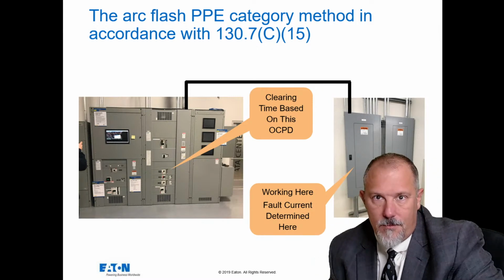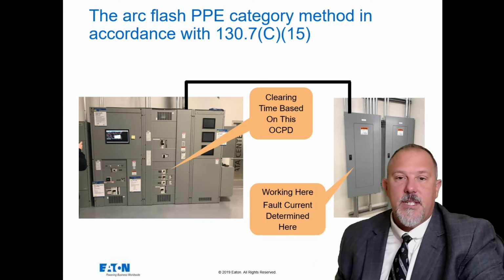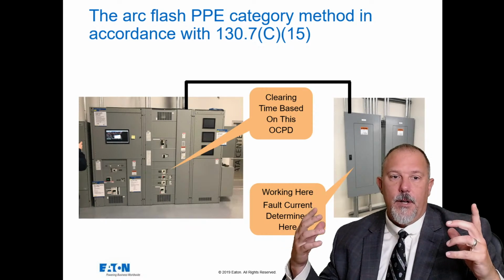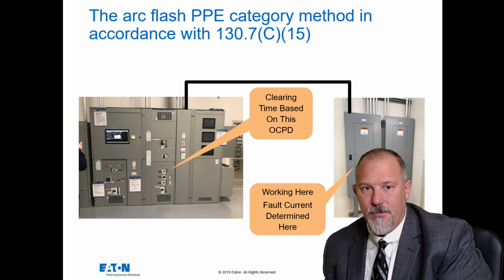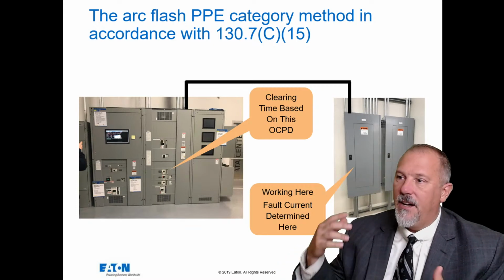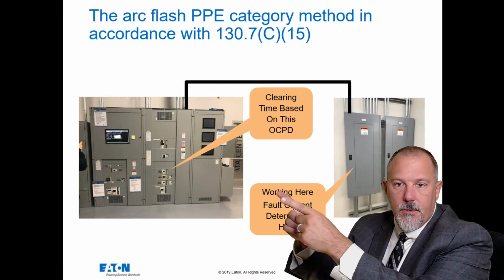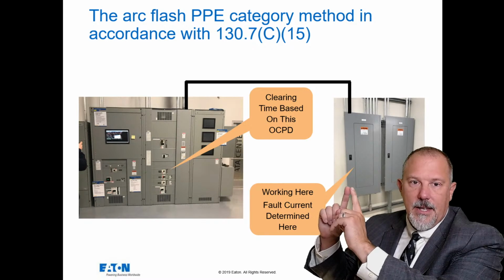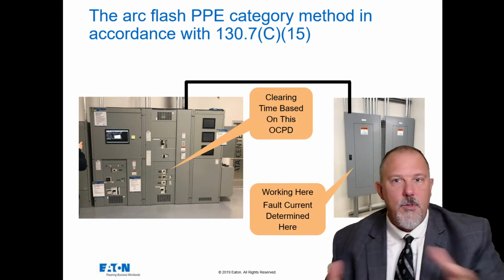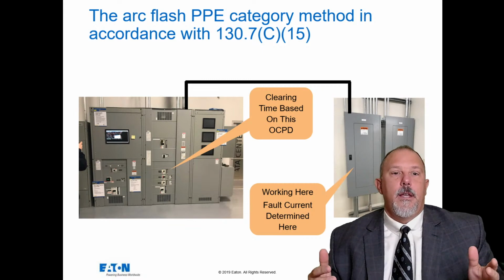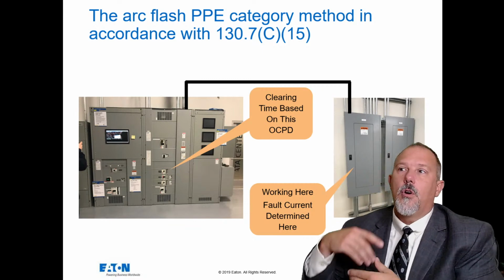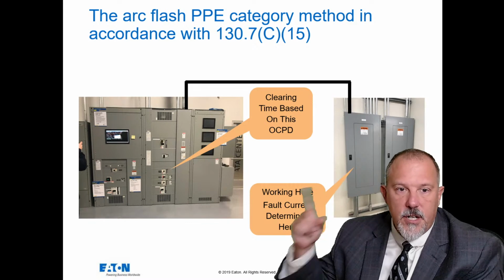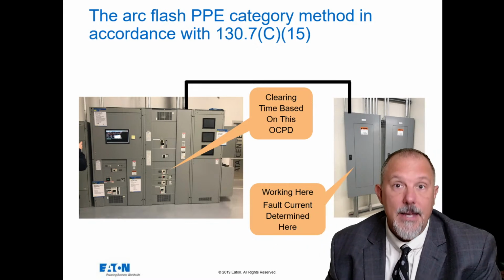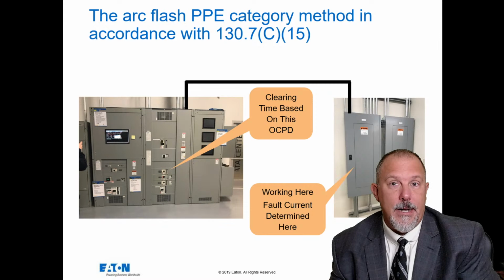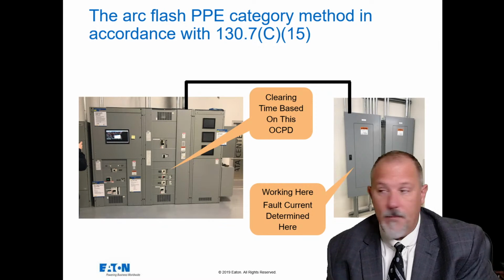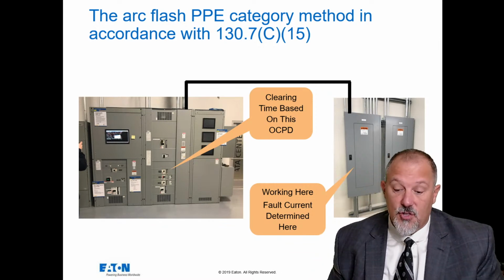Now, if I am series rating a device external and internal, so say I'm doing a series rating of the feeder breaker to this device inside of this equipment, and that's what I'm using for my series rating, the chances of your arcing current being in the instantaneous region of the upstream device is probably high, which would mean I don't necessarily need an arc reduction maintenance switch.